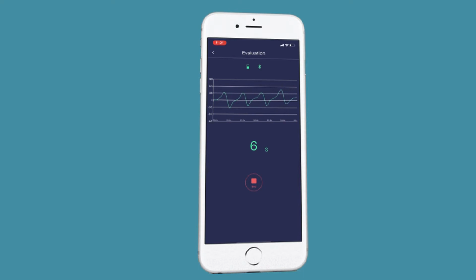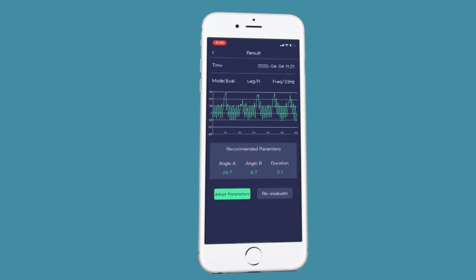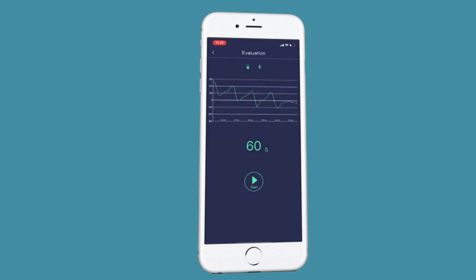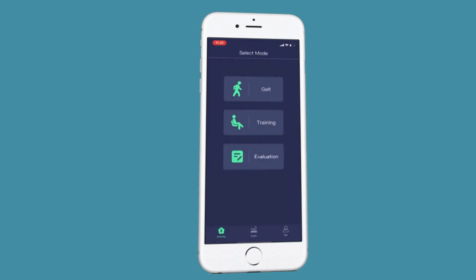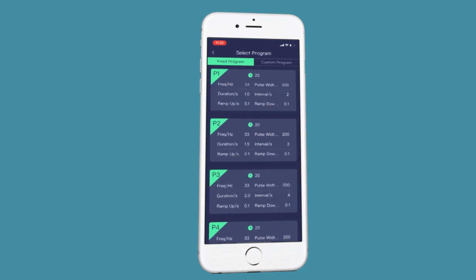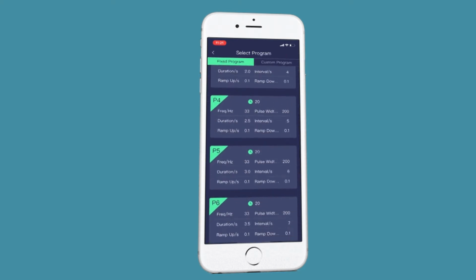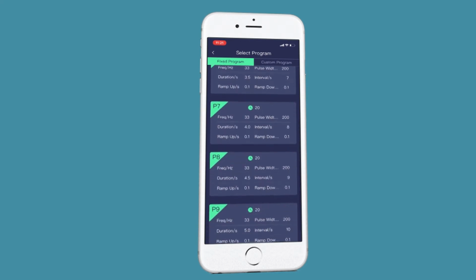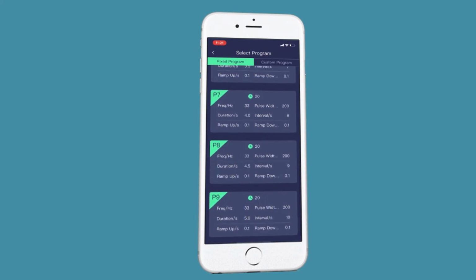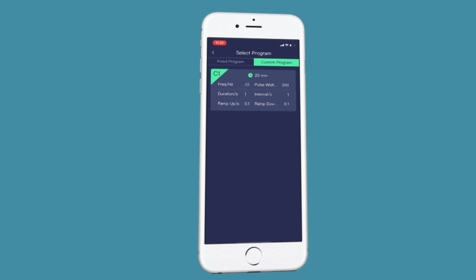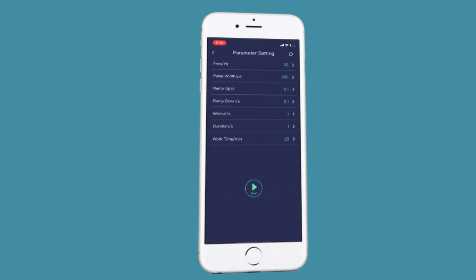At the end of the 60 seconds, the device will complete its data collection and send parameters that are recommended, which you can either adopt or reevaluate. So you can confirm and send the parameters to the WalkAide II. So now the WalkAide II is programmed in evaluation mode. Then you have training mode, and you have some fixed programs that you can choose from, or you can customize a program. So this is your exercise mode.